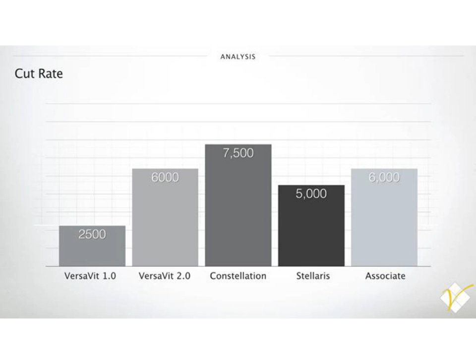And I especially don't know if I want a higher cut rate if it's going to decrease my flow and if it's going to make my core vitrectomy take much longer. But what I was shocked about with the Versavit 2.0 is that even though they increased the cut rates from 2,500 all the way up to 6,000, in the sweet spot, which I feel is 4,000 cuts per minute, you get incredible flow. And this comes from two things. Number one, duty cycle control, where you can have a port-biased open vitrectomy probe so that you're getting more flow, you're closed less often. And you can see how it compares to the Constellation.